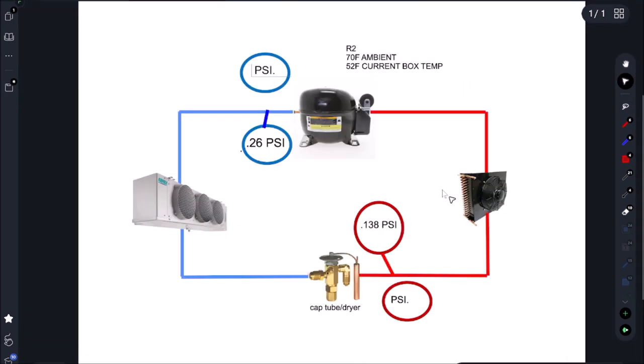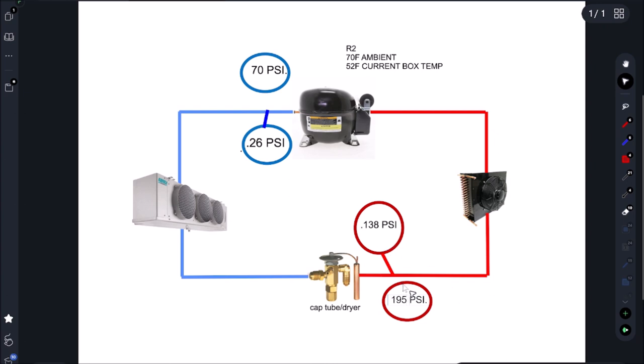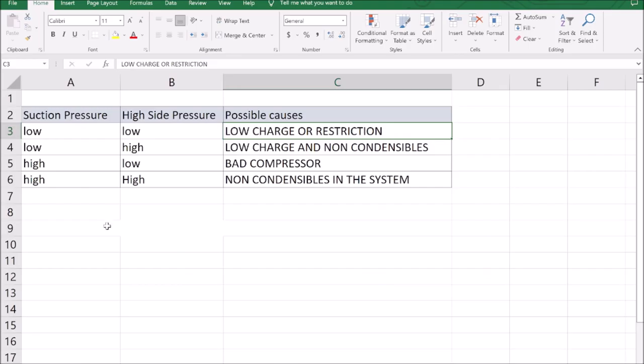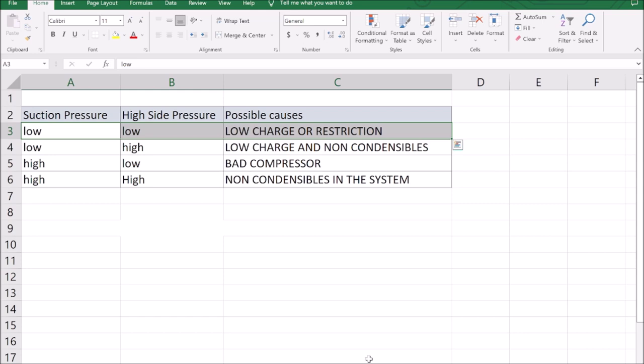Alright, so let's head over to our refrigeration cycle chart and we're looking for 70 psi on the low side, we're getting 26, and on our high side we're looking for 195 psi, we're only getting 138 psi. So what does that mean? Low suction, low head pressure. So now we're going to pull up our refrigeration high low chart and we have low suction, low head, that means we have two issues: either low on charge or a restriction.